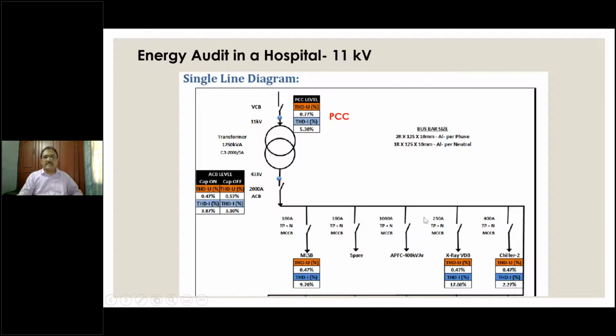So in this SLD, we have also provided to the customer the harmonic level, both in current and voltage at this level. This meets the standard, and therefore at the point of common coupling, this customer need not worry too much about reducing the harmonics, right? Now on the secondary side of the transformer, the harmonics are like this, with capacitor and without capacitor. So typically when we do an analysis or audit, we connect a power analyzer for 24 hours and capture 24 hours of data. You will find them coming when I scroll down. Some of the slides I'll explain to you. We take the 24-hour data, and multiple values and multiple solutions are discussed. So we'll go forward and take a look.